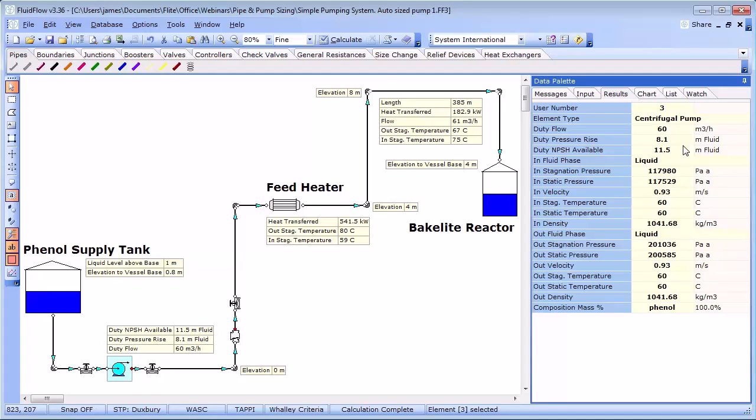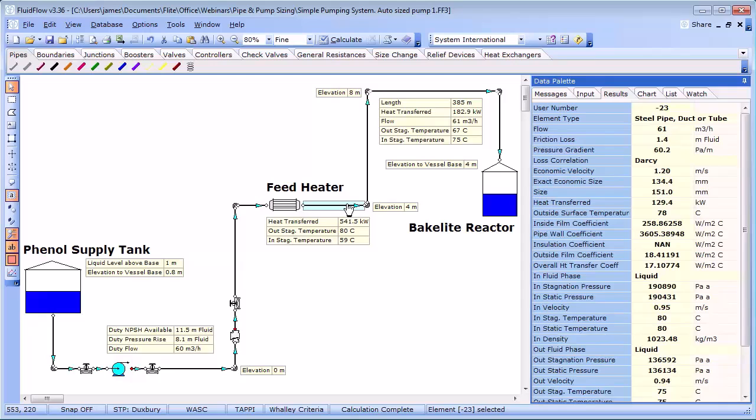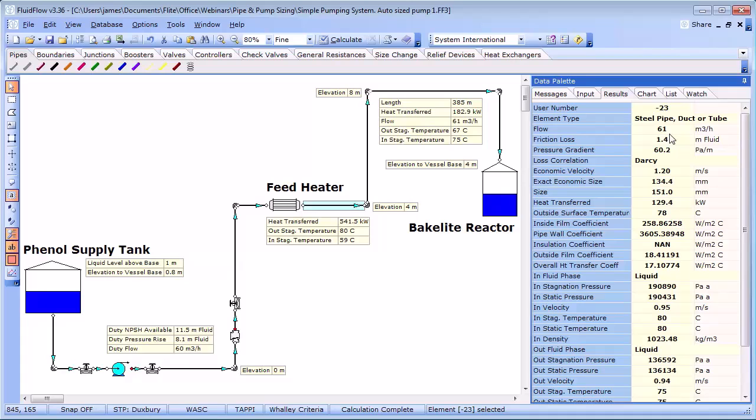Before we fill out our pump data sheet and contact our pump supplier there are other considerations we should make such as: is the net positive suction head available a sufficient margin? The volumetric flow rate after the heater increases. Will this impact on my system design? Start up and shut down. Do we need to drain the line as phenol solidifies at 40 degrees C? Should we steam trace or heat the line? Do we need any relief devices? Can we experience transients? Our recommendation is always leave the pump selection to the pump supplier who will consider many factors such as correct selection of pump build materials, adjustment of water-based NPSH curves for the temperature and fluid you are pumping to ensure no cavitation will occur, ensure that the duty point is near the best efficiency point, correct the pump performance curves for any viscosity effects and so on.